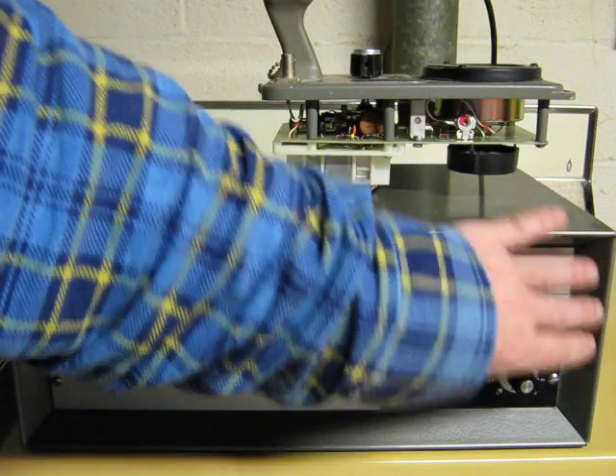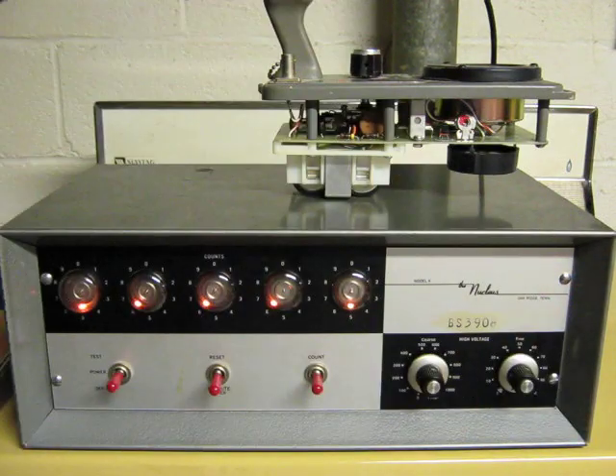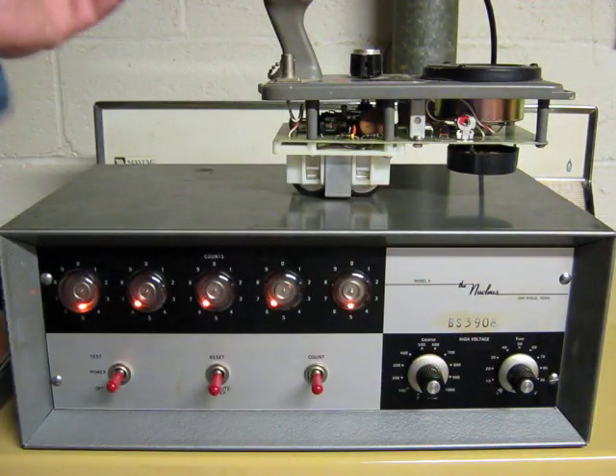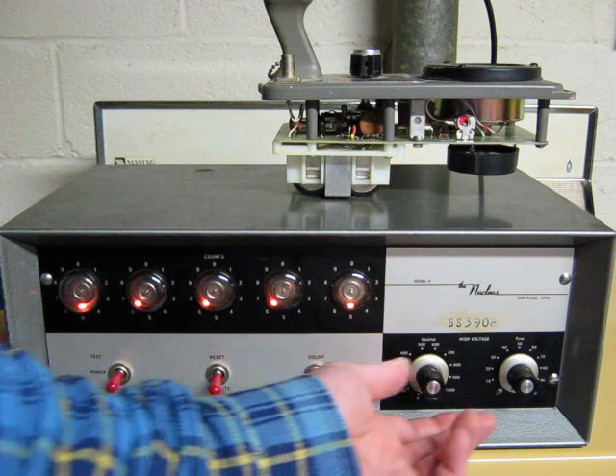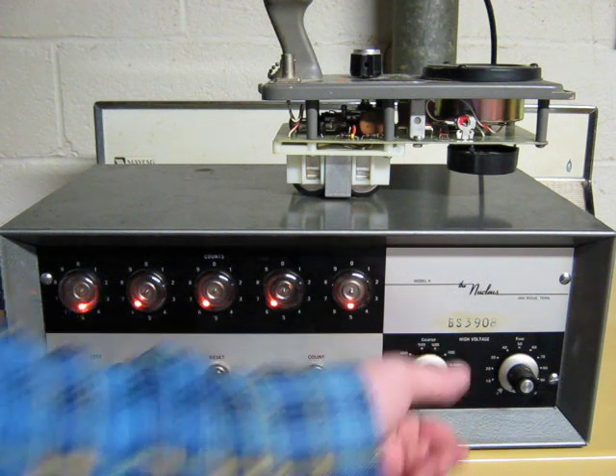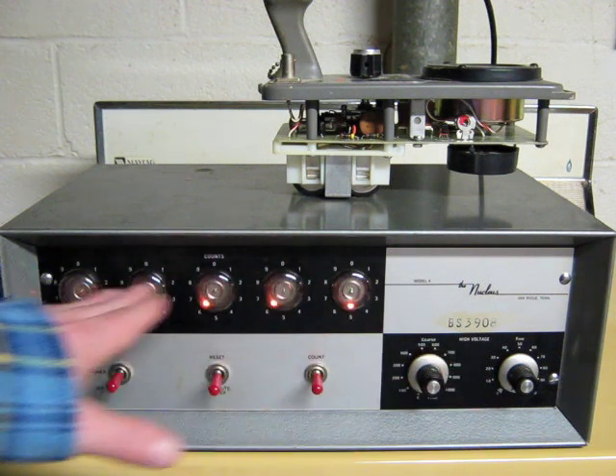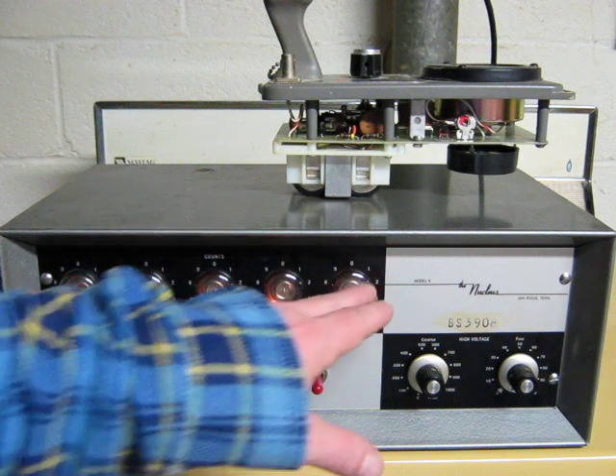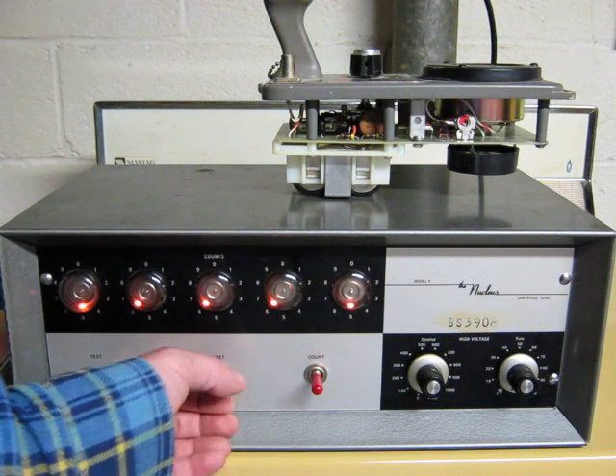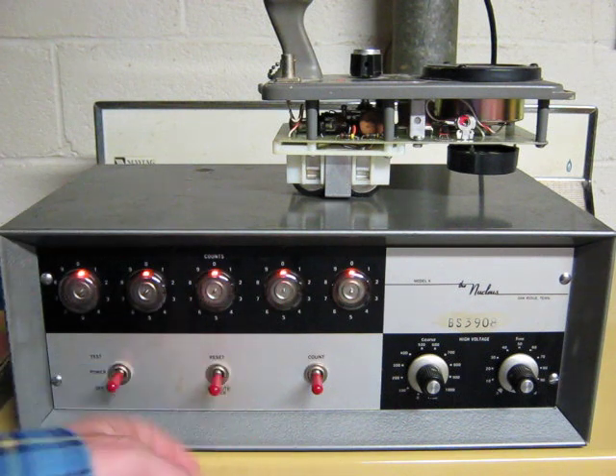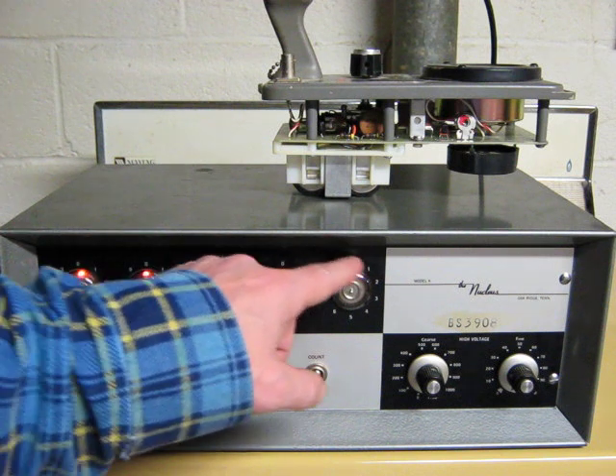So this part is the counter. This part is the power supply for the tube. And right now the tube voltage is set to 0, so it's not going to receive any pulses from it right now. It won't do so until it gets up above 800 volts. The counter is, when you turn it on, set to some random number, which can be reset. Now these all read 0.